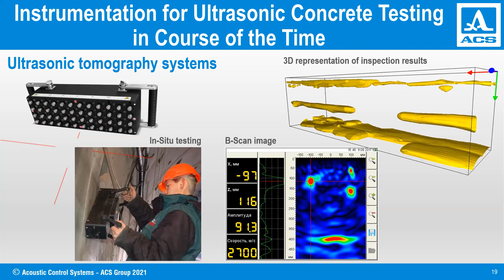Nevertheless, there were very different instruments for imaging. Initially, they were based on regular piezoelectric technology. Later, so-called dry point contact transducers came into the picture, and already in the early 2000s, there were phased array instruments for imaging on site. Finally, it came to 2 and 3 dimensional imaging of the structure, and I would say step by step, at least from the technical point of view, ultrasonic instrumentation for concrete is reaching the state of the art of regular phased array instrumentation for metal testing.